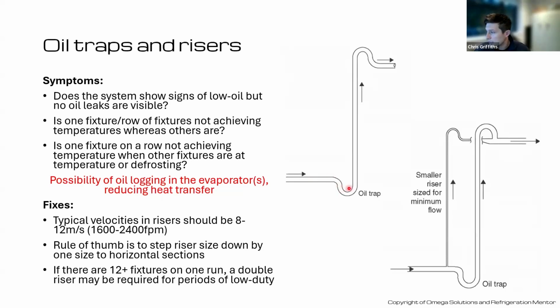So let's say it makes a nice flat oil trap. As with any trap below your sink in your kitchen, you have water in there to stop smells coming back. Well, same principle here. We want to make sure that gas builds up behind to enough velocity to then dislodge that oil and force its way up.